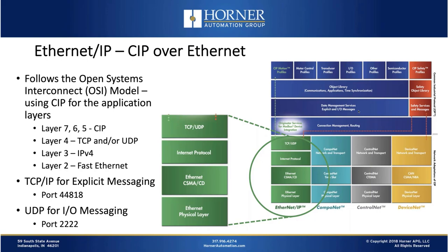From a port standpoint, there are two ports to mention. For explicit messaging — the occasional, asynchronous messages — TCP/IP is used with port 44818. TCP/IP messaging takes fair overhead, but that's okay because these messages are only sent occasionally. For implicit messaging — the I/O type messages sent on a continuous basis — UDP and port 2222 are used. UDP makes sense here since it has less overhead. Unlike TCP, UDP has no guarantee of delivery, but that's not a problem because if an I/O type message is lost, there's always another one coming in a few milliseconds.